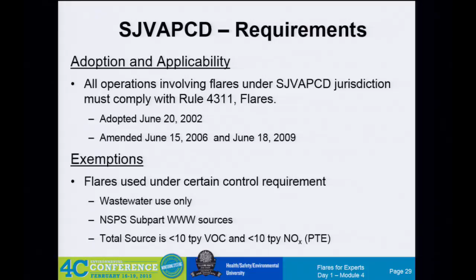It has some really interesting things. Probably the most amazing is this Coanda effect. It's the only rule in the country that uses the pressure-assisted Coanda effect as an exemption. In the rule, which is a SIP-approved rule under an Air Quality Management District, this is EPA SIP-approved: if there is a Coanda effect, a pressure-assisted flare, you're exempt from the 60.18 tip velocity requirement.